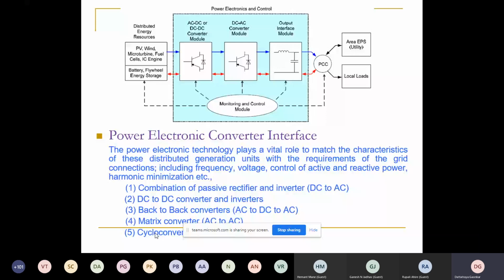Remember, when converting solar power, you go from DC to DC, then DC to AC, or when converting AC to DC, then DC to AC. Why can't you convert AC to AC directly? Why not utilize a topology like a matrix converter to convert AC into AC directly, avoiding a conversion stage in between? This is more efficient, but it has its own issue: you don't have the inherent separation that a DC link provides, like in back-to-back converters.